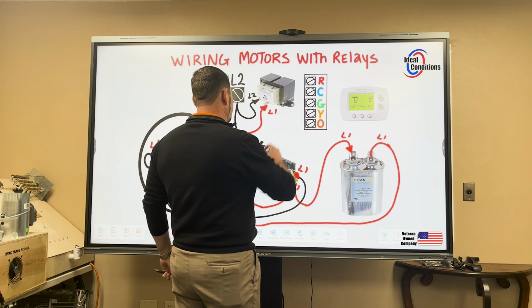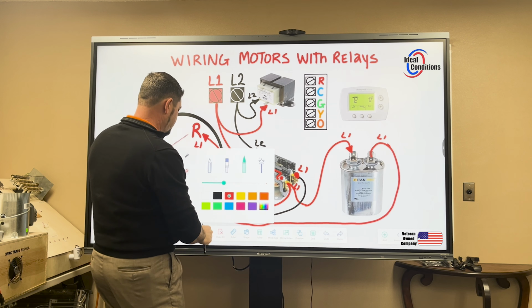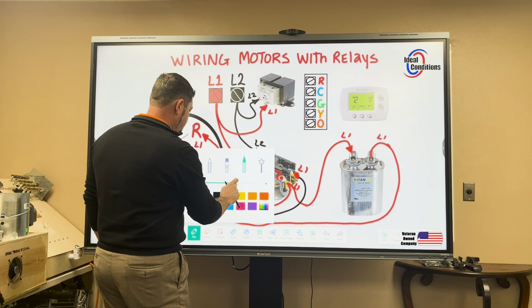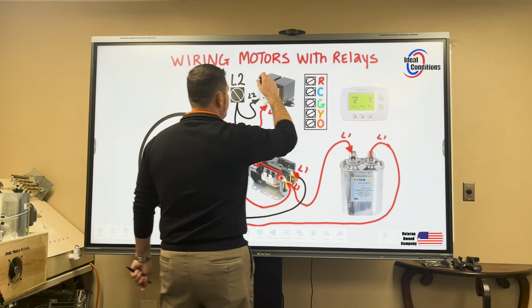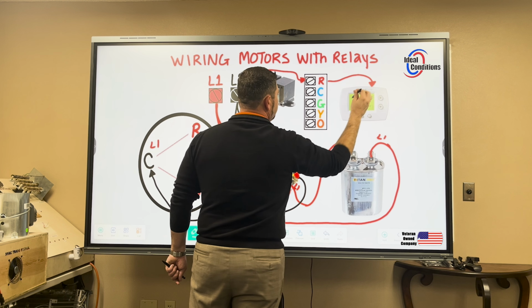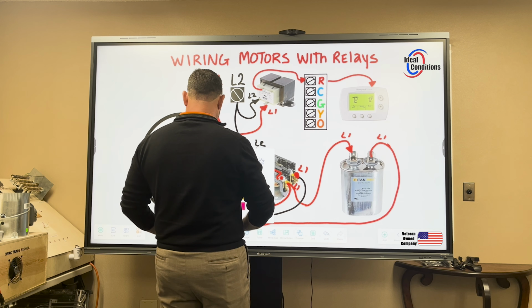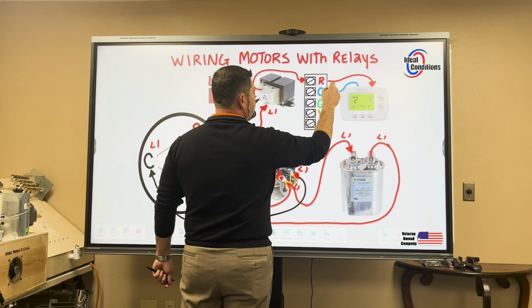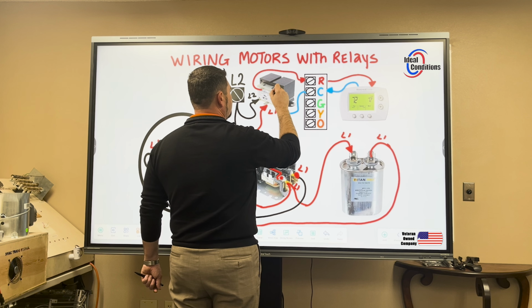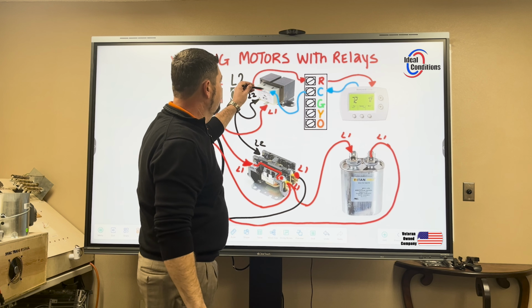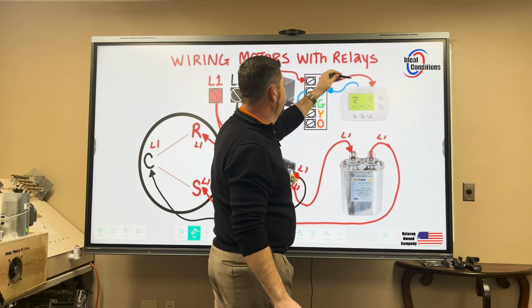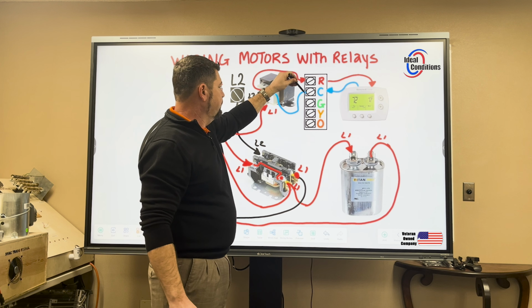We're going to come out with 24 volts, which will come out of here, land on the thermostat, and then common back to the board, or the terminal block, and then out of the terminal block back up to the transformer. So we have output, input, output, input, output.